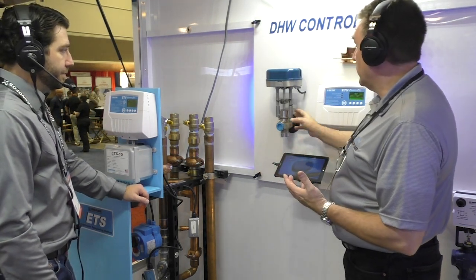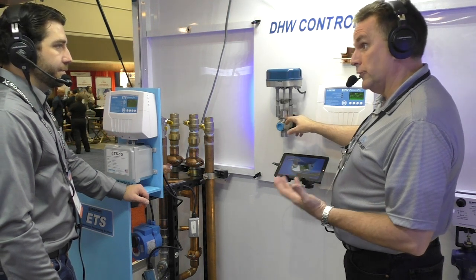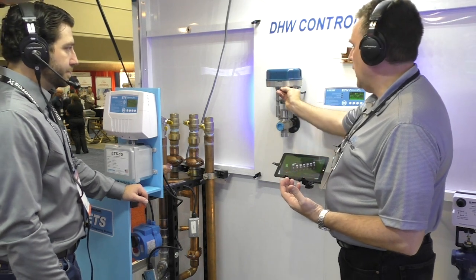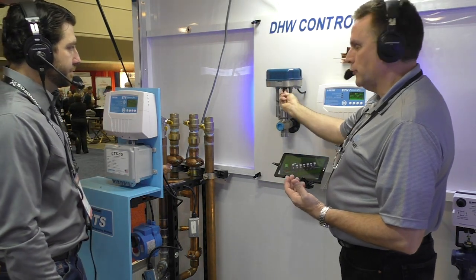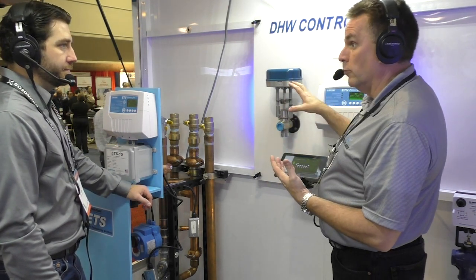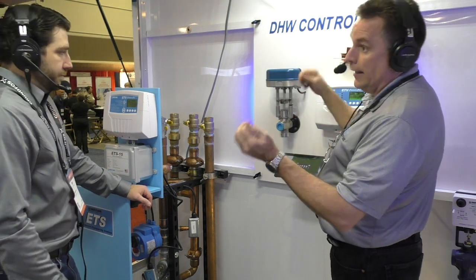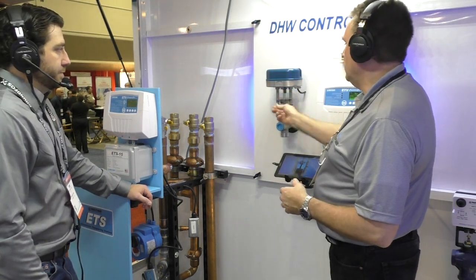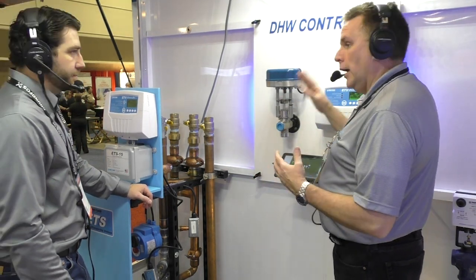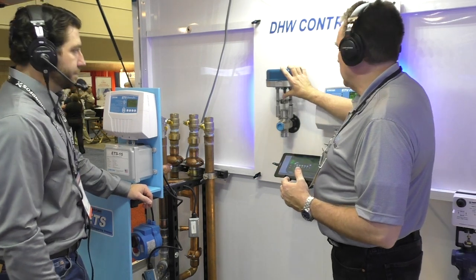Yeah, again, heat timer on all their controls, whether it's this control or any of our other boiler controls, simplicity is key. And if you take a look at the actuator here, it's only mounted onto the external of the valve body by a U-bolt, so it's easy to service. It does have a manual adjustment here, so that if it does fail in a case like that, you don't need to worry about having bypass piping around the valve and undoing valves and stuff like that. You can put this into a full hot position, turn down the thermostat on the water heaters, and you'll be good to go until we can send out a replacement.